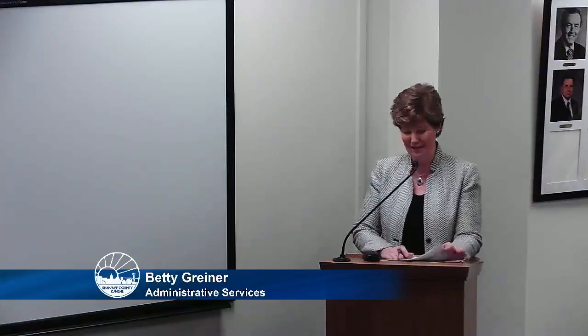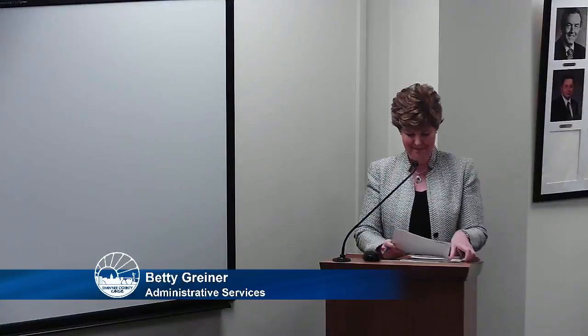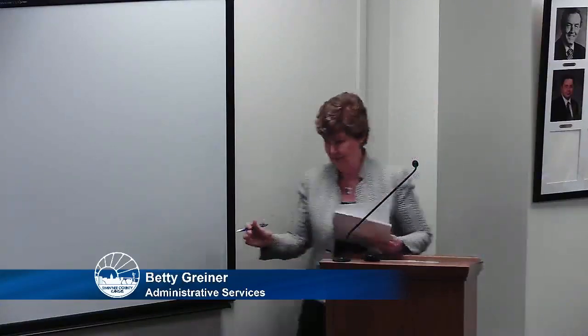Bill can explain the technical part of it. Currently the Expo Center provides the chilled water to the Manor Conference Center, and has for a number of years. Originally Manor had its own system, but when that failed, the Expo Center had a system able to supply it. The design going forward on the Expo Center renovations would switch that system away from chilled water to rooftop units, which would necessitate a new system being put into Manor as well.